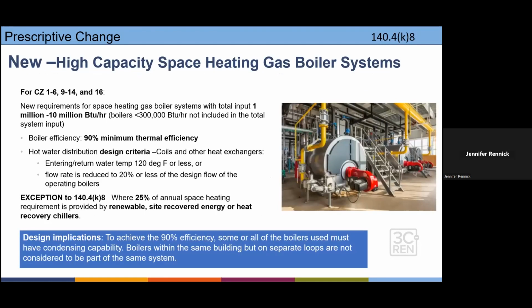And when it comes to the high capacity space heating gas boiler system, this is a system where you would not go all electric; natural gas is the fuel. They're saying, if you still need natural gas for these types of systems, then the boiler efficiency has been bumped up to a 90% minimum thermal efficiency. The threshold on the equipment has been lowered, and it is climate zone specific. There are a few exceptions, and the basic design impact for mechanical engineers is that they're going to have to consider system layout, partly because boilers within the same building but on separate loops are not considered part of the same system. So you have some trade-offs you can make with efficiency and how the whole system layout is set up.